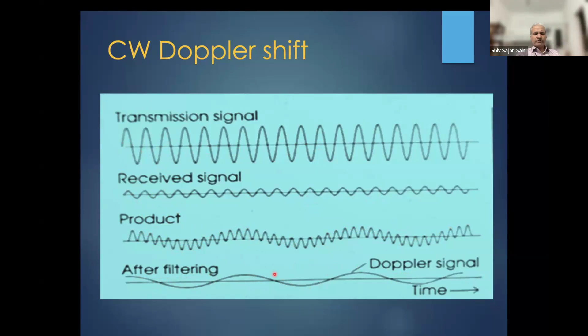So this is the visual depiction. This is the transmitted signal. This is the received signal. Once you overlap these two, the machine has software to overlap them, then it smoothens it out after filtering. This is the Doppler shift, and this is how the machine interprets that there is a difference in the velocity of the signal from the transmitted, and the velocity of the signal is calculated based on this Doppler shift. So how do we use that?